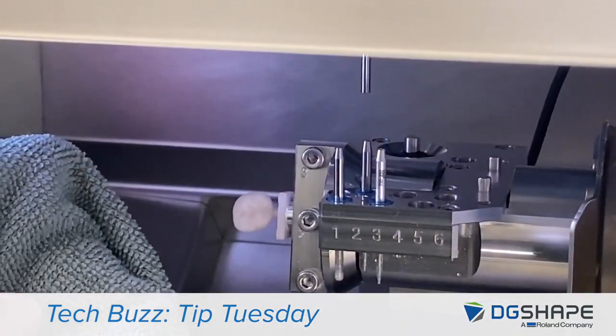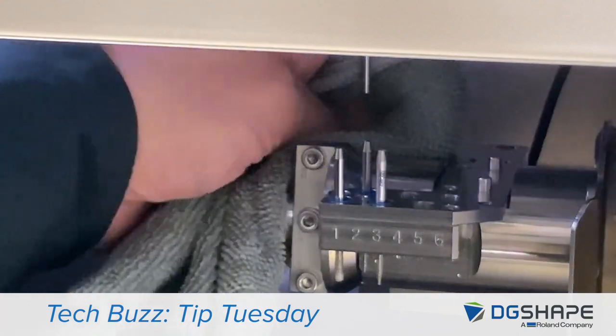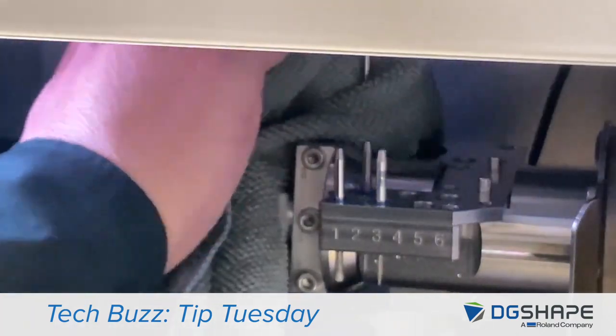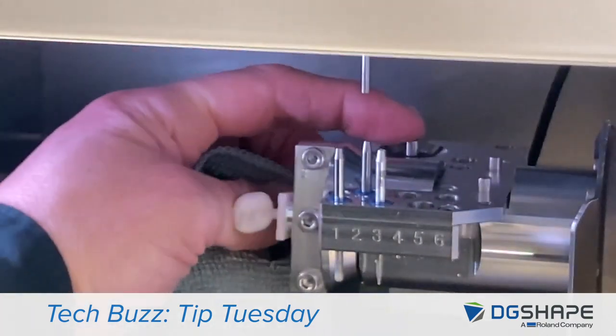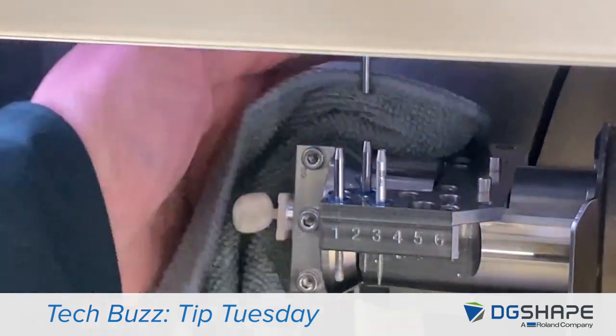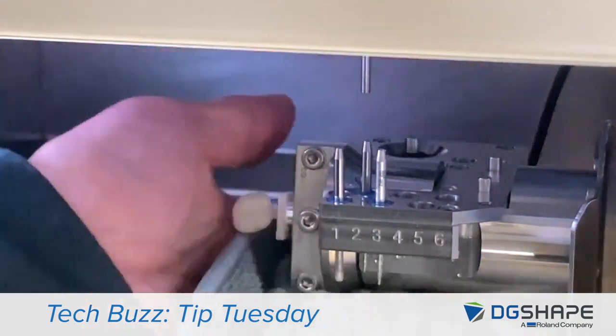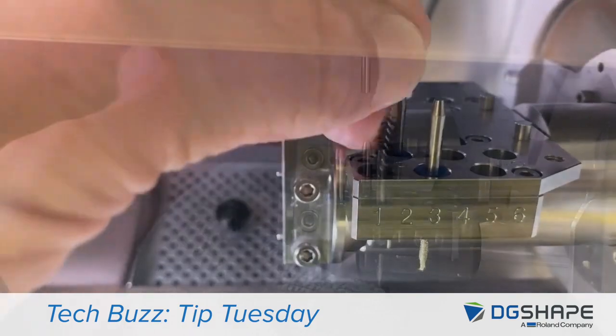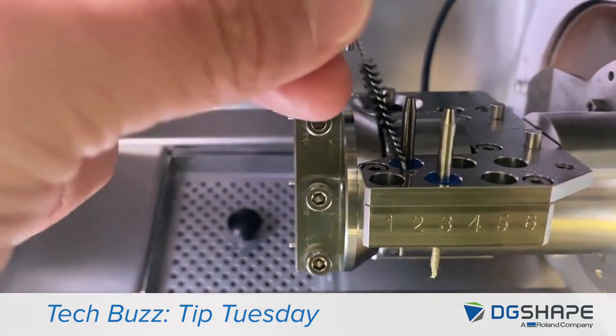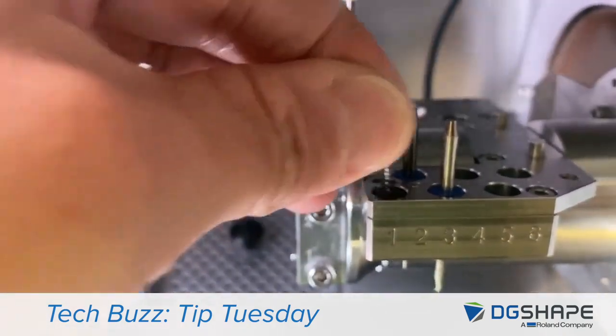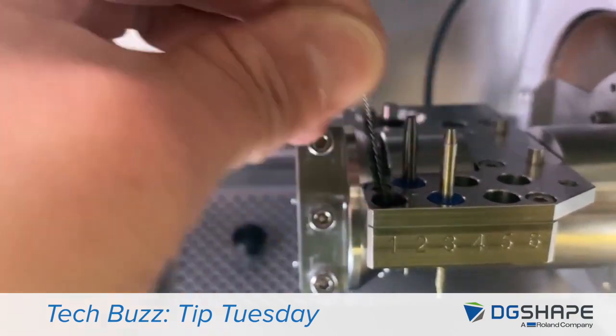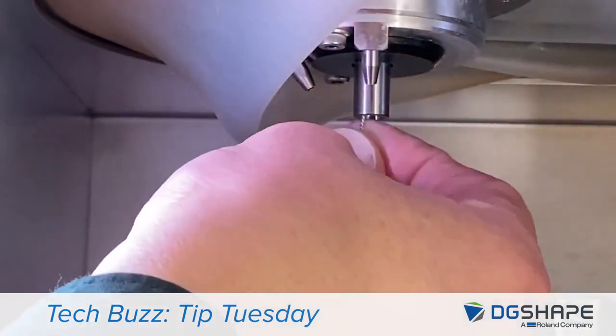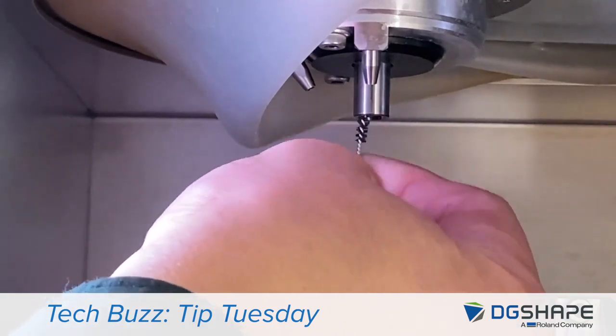Let's go ahead and clean the entire ATC assembly. Inspect the sensor. Make sure it goes in and out and it returns to its home position. Now, go ahead and clean all the positions 1 through 6 with a little brush. Go inside and clean the O-rings. Also, with a small brush, always remember to clean inside the spindle.